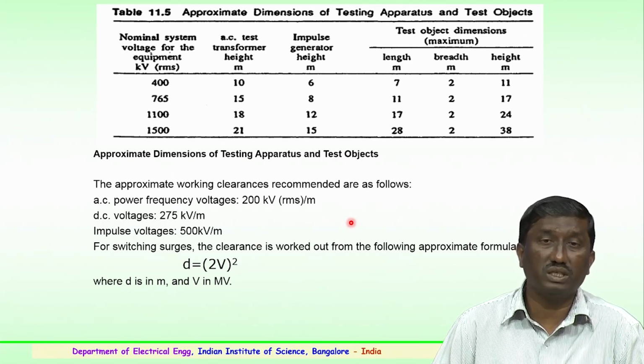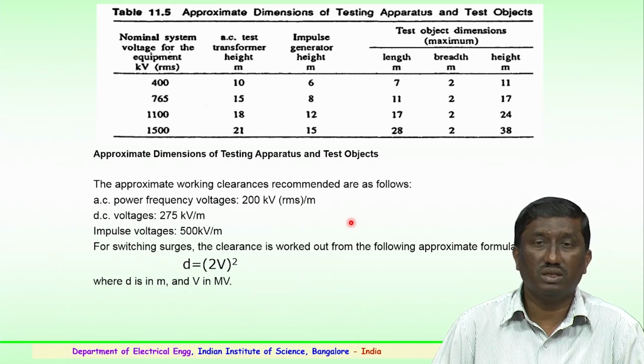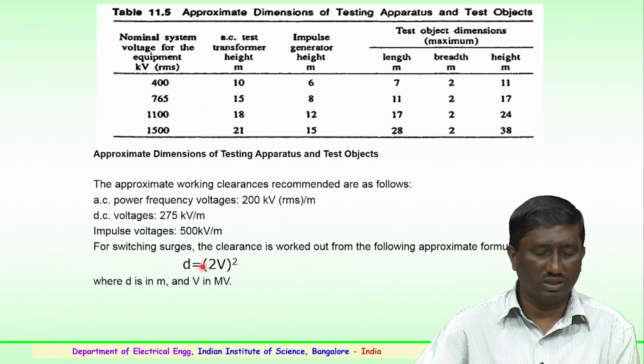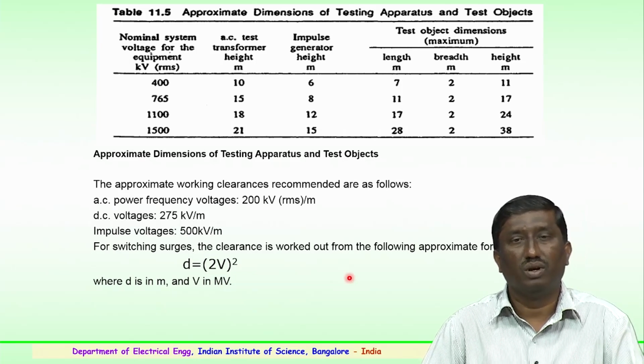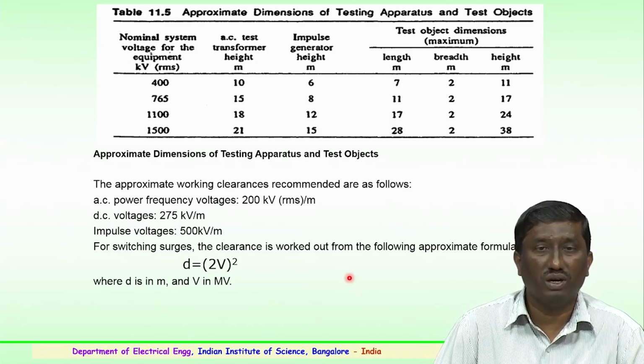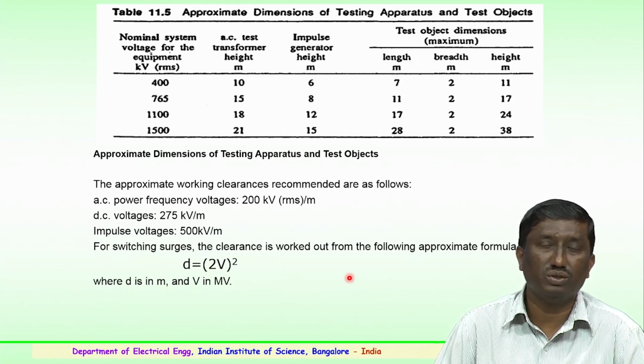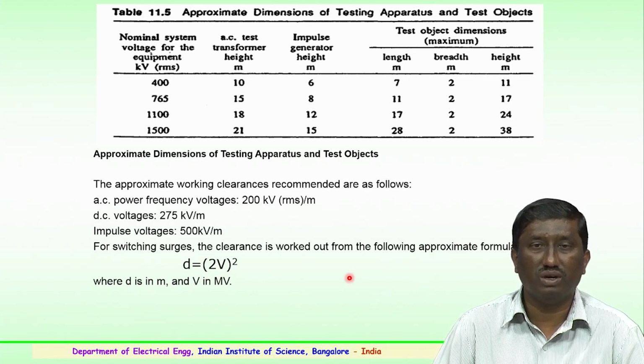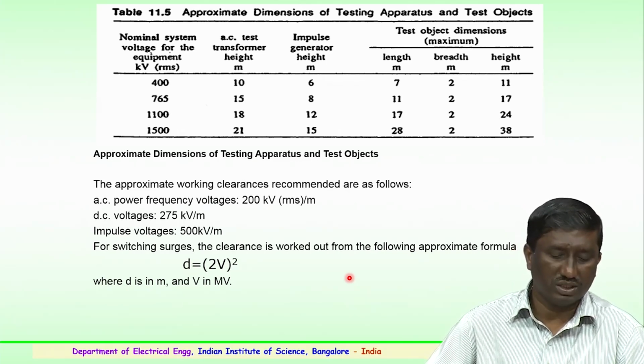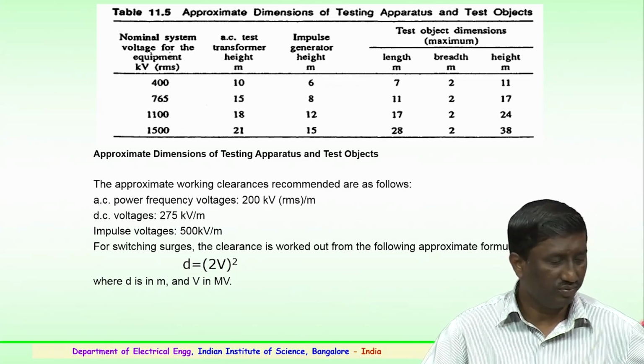For switching surges, the clearance is typically worked out from the simplest formula, D equals 2V squared, where D is the distance in meters and V is in million volts. So, as per the voltage level, this distance or clearance is to be followed. The simplest equation.